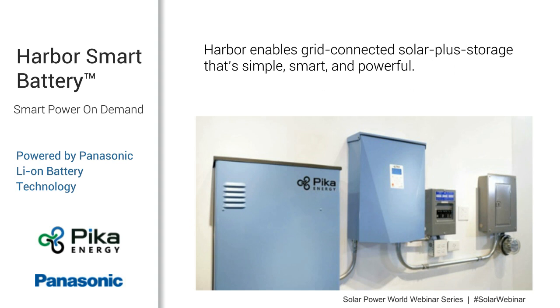With the Harbor Smart battery, this enables grid-connected solar plus storage that's simple, smart, and powerful. So those are the three main things to remember about this. It's simple to install, simple to commission. There's not even a separate communication cable between the battery and the inverter. It's just all connected over the power line carrier. So you see that one connection point there to the DC breaker inside of the inverter on the left side there. That's the battery connected to the inverter on 10-gauge wire. So putting these systems in is really simple, really plug and play. It's smart to work with operational modes that are pre-configured into the Energy Island system, and you get more power for those islanded loads when you're using it for backup power than you would with a system that requires an auto transformer.